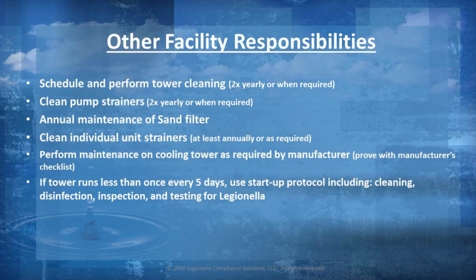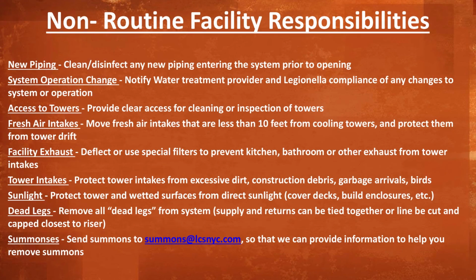Remember, if the tower runs less than once every 5 days, you must use startup protocol, including cleaning, disinfection, inspection, and testing for Legionella. There are certain scenarios that are more on a case-by-case basis that the facility must also take care of. If you have construction going on in the building, new piping must be cleaned and disinfected before using it in an existing cooling tower system. If your system operations changes, such as you're now running on the weekends, shut down for the season, or now operating year-round, you must notify the water treatment provider and LCS inspector so they can change your water management plan.